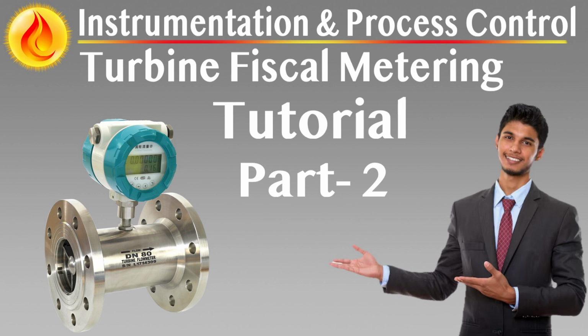Thermal relief valves must be installed on any liquid-filled sections where thermal expansion could cause overpressure, especially in systems with block valves or closed ends. These relief devices must discharge to a safe collection system. During factory testing or site commissioning, turbine meters must be replaced with spool pieces manufactured to the same specifications as the skid piping and supplied with matching flanges and gaskets. All headers and branch lines must include mechanical flexibility to absorb expansion differentials, especially when some meter runs are offline.